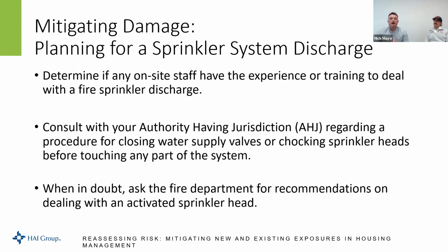That goes without saying: when in doubt, ask the fire department for recommendations on dealing with an activated sprinkler head. So if I was a property owner or a building manager, housing authority representative, the first thing I would do is ask a representative like Paul, what are you comfortable with me doing? The follow-up question from Paul most likely would be, well, what type of building is it? What type of sprinkler system is it? Who on site has experience or training to deal with a fire sprinkler discharge? If no one really has the experience, knowledge, or training, then they're going to say, in an emergency or even in an activation of fire alarms, just get out and meet the fire department at the front door.